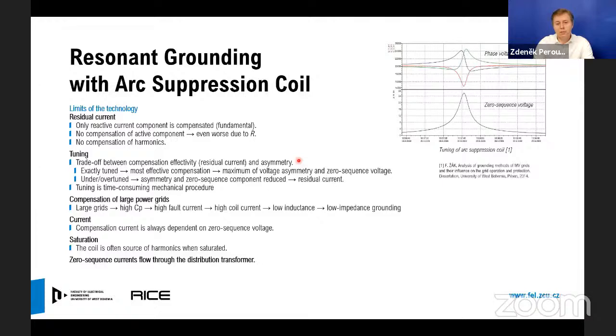The problem is also the compensation of large power grids, which leads to low impedance grounding, having several consequences within the protection of such a power grid. The compensation current, which is produced by the arc suppression coil, is always dependent on the zero sequence voltage. The coil is often a source of harmonics when saturated, and there is one important drawback: the zero sequence current flows through the distribution transformer and loads it.